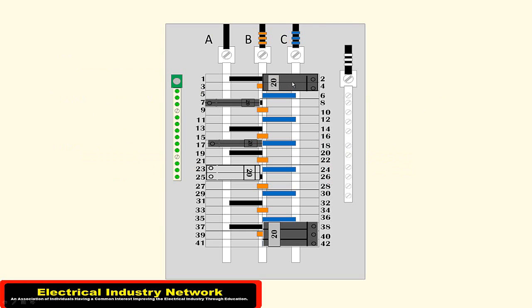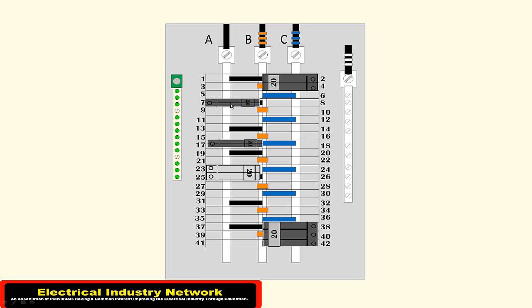This particular breaker up here on circuit 2 and 4 needs to be a straight 240-volt. You can't have a 120/240-volt breaker on that. This breaker here on number seven has to be a 120. They come as 120, that's all you can get on a single pole. Same thing, another single pole.